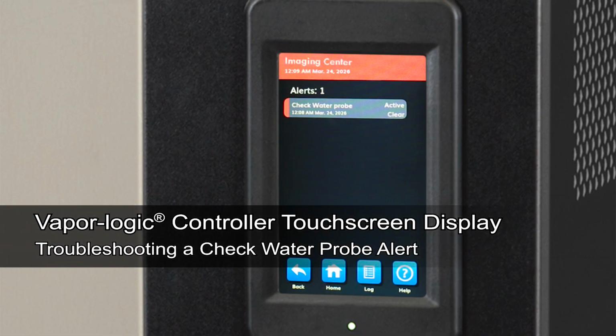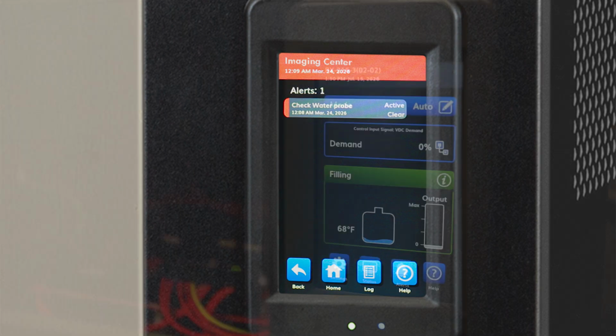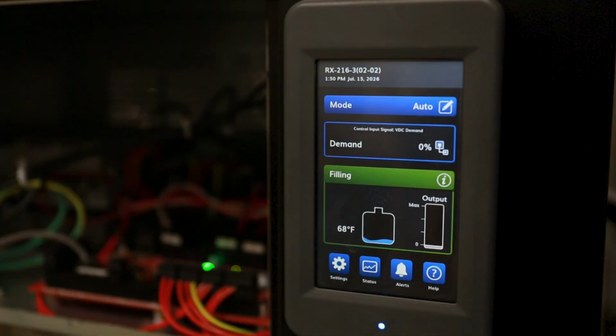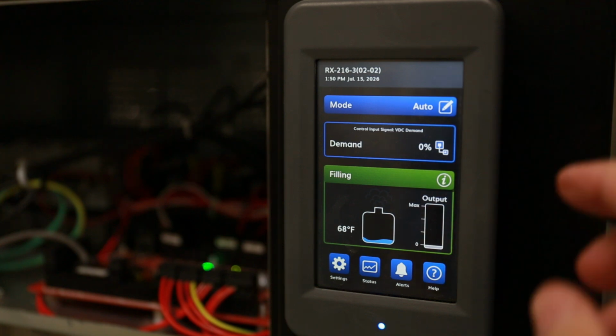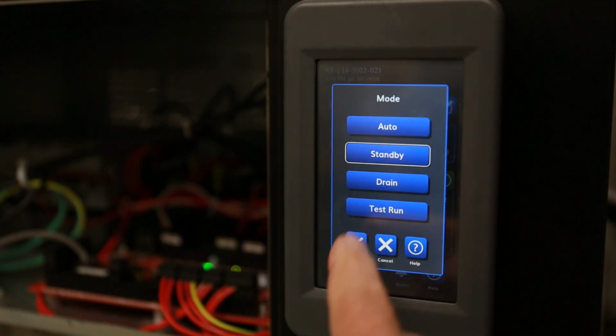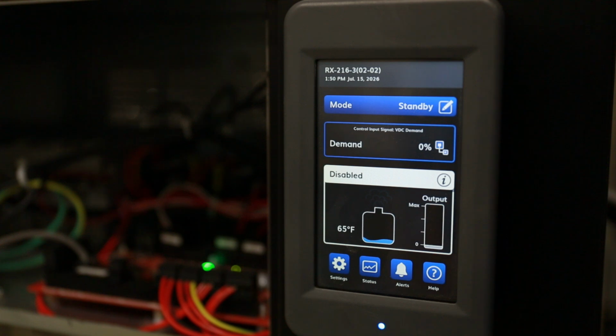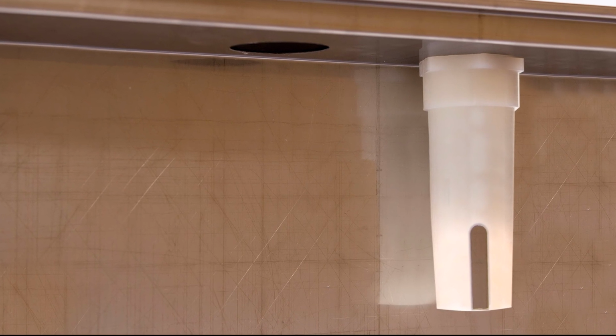Let me show you how to diagnose a check water probe alert on a humidifier that has a VaporLogic controller touchscreen display. Step 1 before any troubleshooting is to put the humidifier in standby mode to keep it from starting up. The water level probe assembly is located inside the tank, and the probes are inside of a cup.